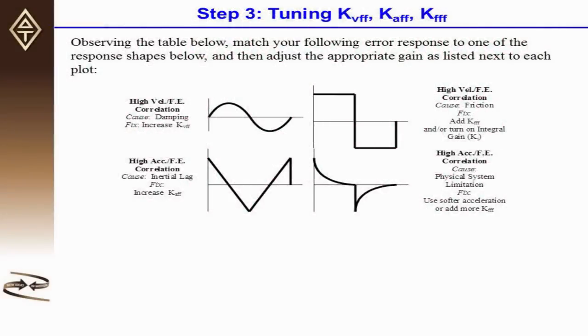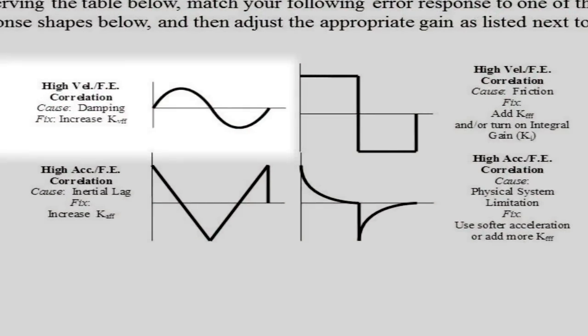Let's look at some example cases. The top left diagram shows a high correlation between the following error and the commanded velocity. That is, they are essentially the same shape. This is due to damping in the system. To compensate for this, increase kVFF.